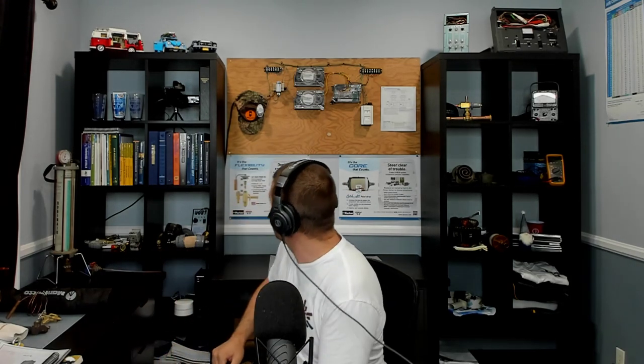I was recently having a discussion with a guy at a counter that I met behind a supply house that recognized me from my videos. And we were having a discussion about airflow. Airflow is one of the hardest things to accurately measure. So the most important thing, in my opinion, my experience, is that you have to understand that nothing is perfect, okay? Let's just say that you're going to use a hot wire anemometer and you're going to traverse the duct where you basically... Here, hold on. I have one, so I'm going to grab it.